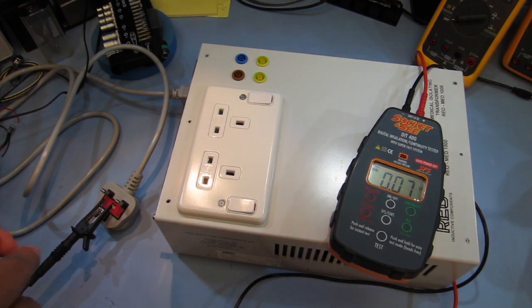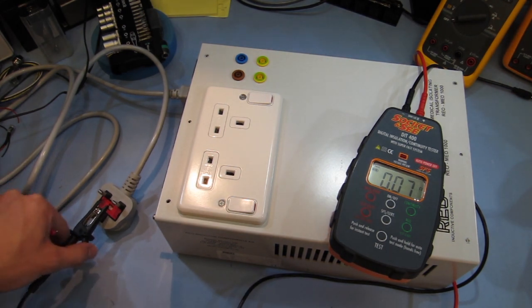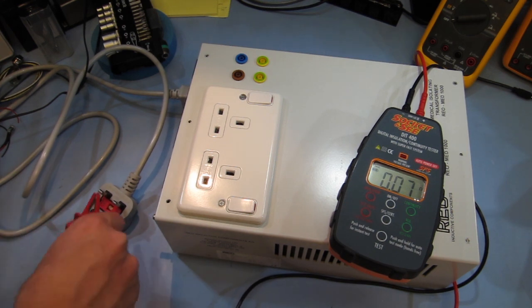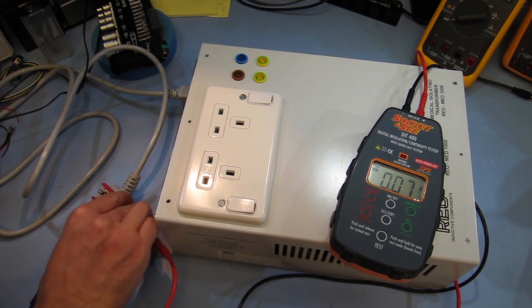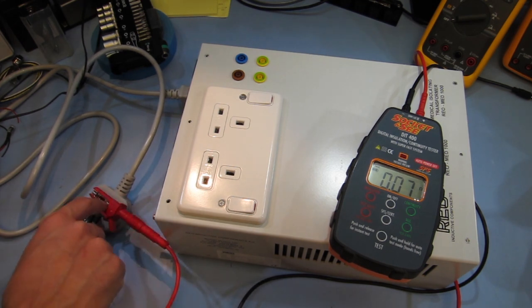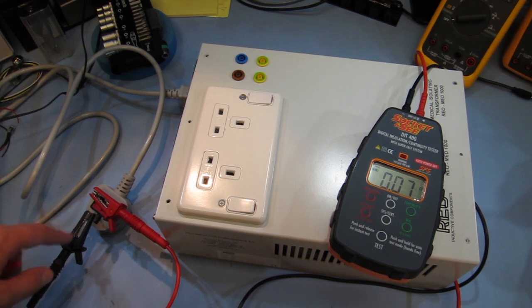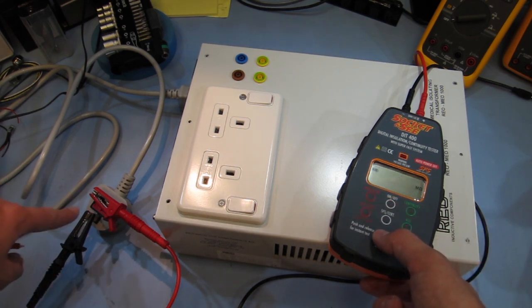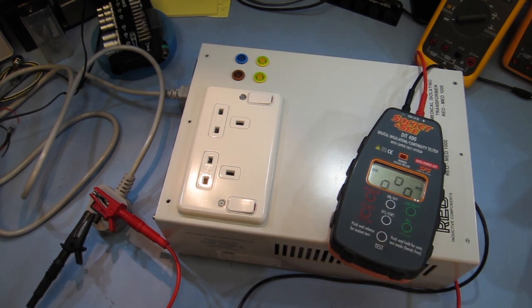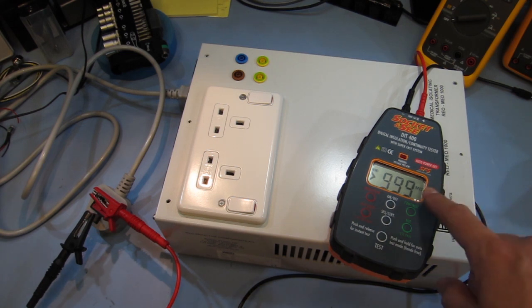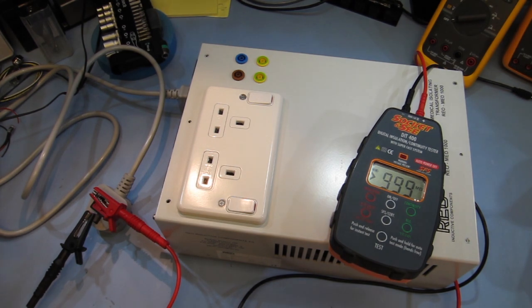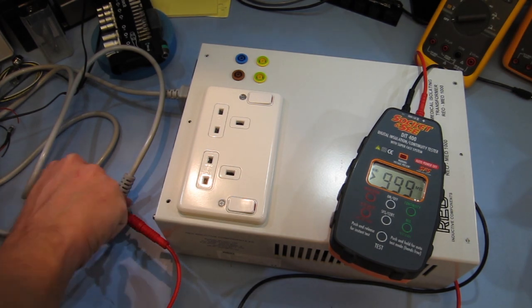Next, we probably want to do an insulation test just to make sure that we haven't compromised the insulation between the incoming mains and the chassis. So I'll put this across the two line conductors and across earth, and we'll put it on insulation test mode, and this will put 500 volts across and measure the impedance. And we can see here it's reading greater than 999 megohms. So we haven't compromised the insulation resistance here at all.